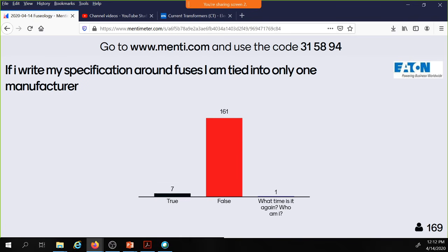So the key thing, remember, usually when you'll see a specification for equipment, it'll tell you class J, class L, class T fuses, and they'll tell you the size. Because of the nature of how we list these devices and how we make products, any of the 3 manufacturers out there, you can put their fuse in those holders, but I know who you're going to pick. But in any case, you can put any fuse in those holders because they're really built around the class fuse, and the class designation of a fuse will dictate the size of that fuse and how it's mounted, so that any fusible switch or any holder that will accept a certain class, you know that any one of the manufacturers who make a fuse, you can fit in that hole. But again, I know who you're going to pick.